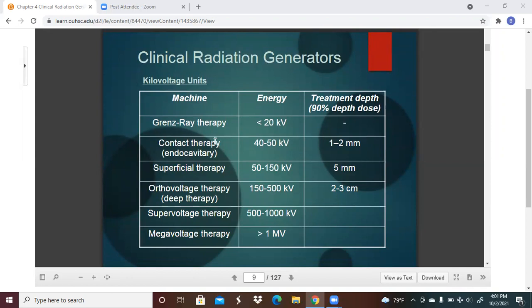All right. So here we have the type of machine, the energies that it produces, and then we have the treatment depth, or 90% depth dose. So you can see there the Grenz-ray therapy is less than 20 kV. Nothing there to remark on as far as the treatment depth. Contact therapy, endocavitary, 40 to 50 kV with 1 to 2 millimeters, 90% depth dose, so that's not a lot.